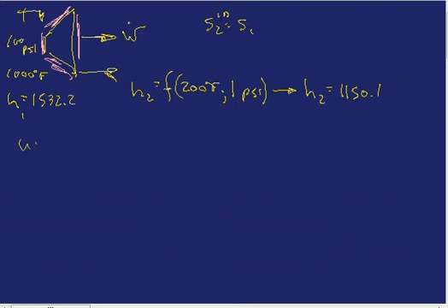So the work that you got out of the turbine, and that's the real work because we measured the temperature coming out, the real work per mass, from your energy balance, is 1532.4 minus 1150.1, which equals 382.3. Oops, sorry, I first misspoke the number; it is 1532.4. So that's 382.3 BTUs per pound of steam that goes through the turbine.